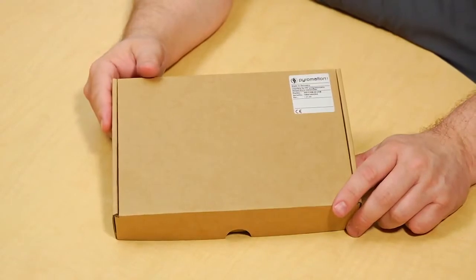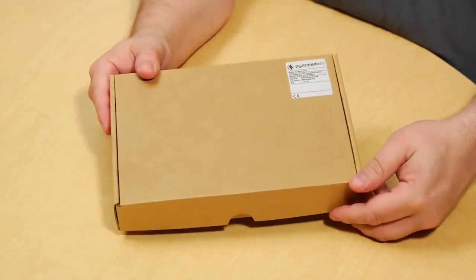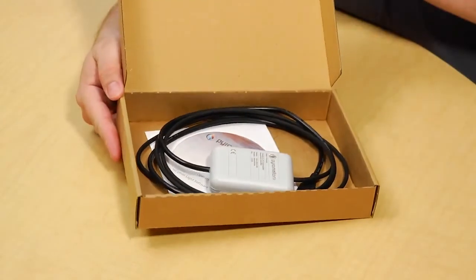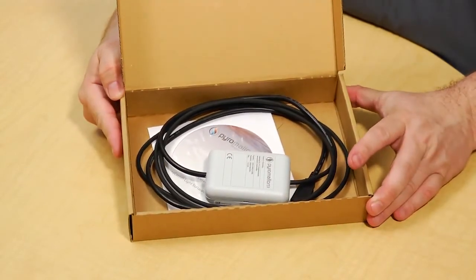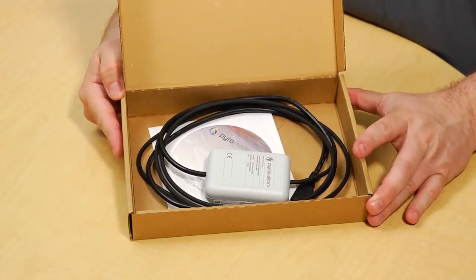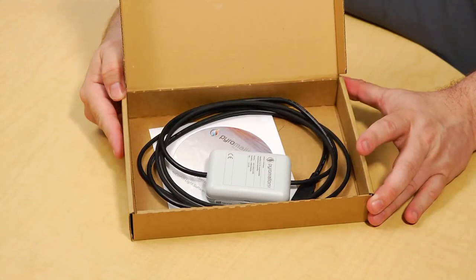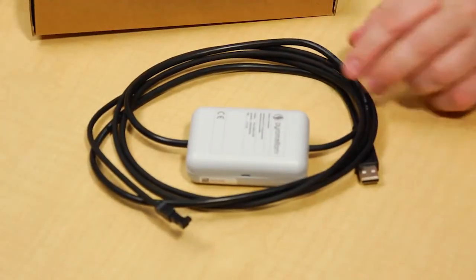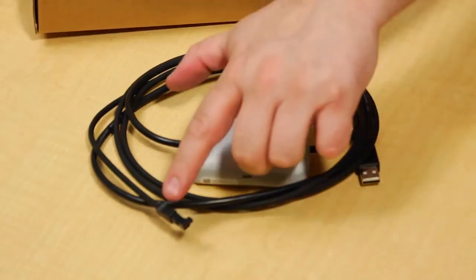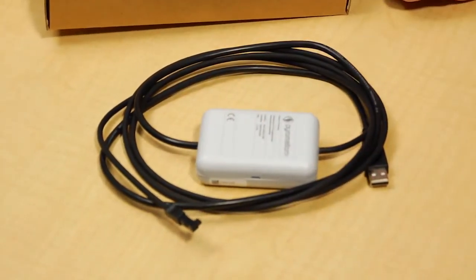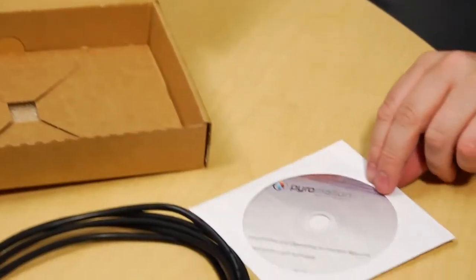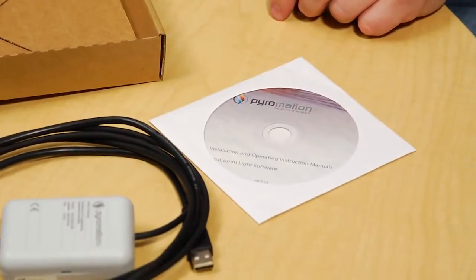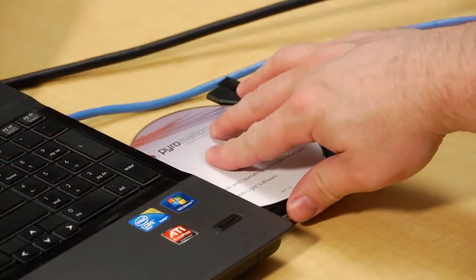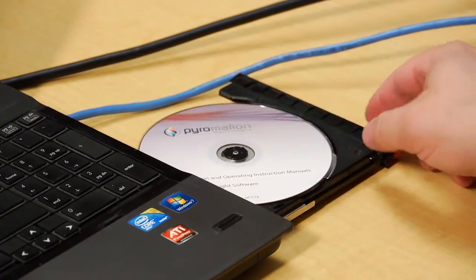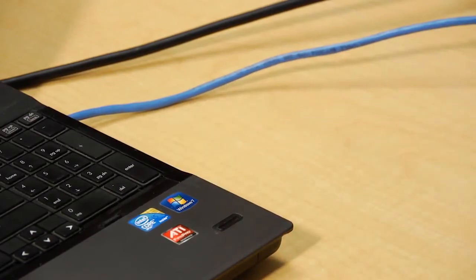This is the 440 transmitter communication cable kit that can be obtained through a local rep or distributor in your area. Please contact Pyromation to find out who that rep is. Here we have the communication cable, which has a USB connection and a connector for the transmitter, along with the Transcom Light software. When installing the software from the disk, insert the disk into the computer.